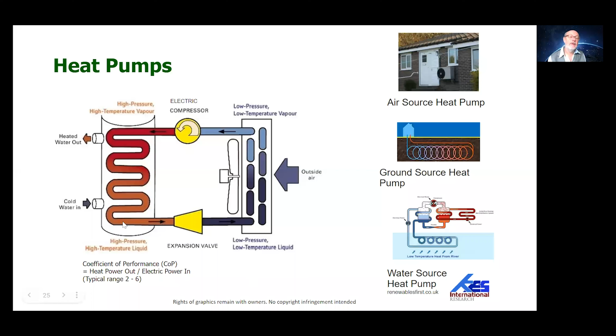So this technology, huge amount of interest, huge amount of research has gone into heat pump technology in the past 10 years or so, although the technology itself is much, much older than that. But efforts have gone into improving efficiency and particularly increasing the temperature of the output side. So with heat pumps, you have something called the coefficient of performance, which indicates how many kilowatts of energy output you get for each kilowatt of energy input. So if you have a heat pump with, say, a coefficient of performance of 3, then that means you put 1 kilowatt of electricity in, and what comes out is 3 kilowatts of heat.